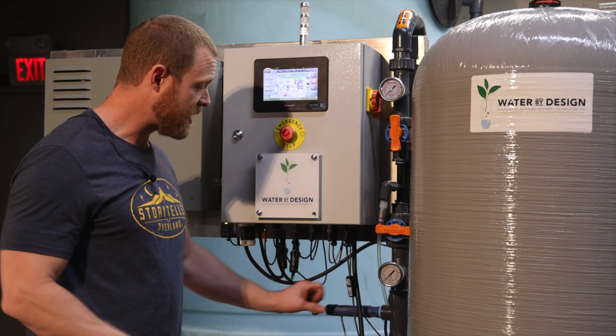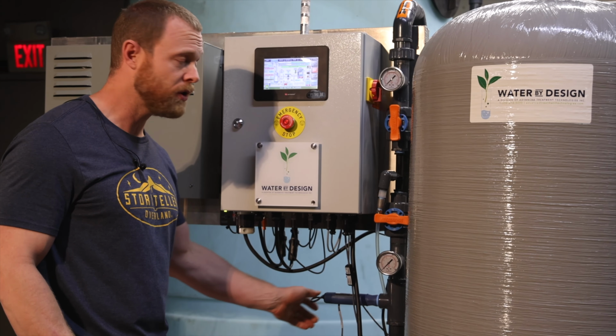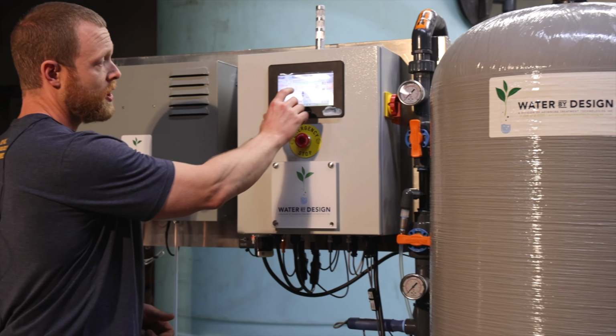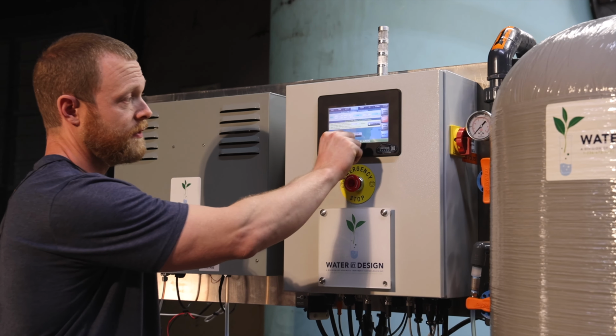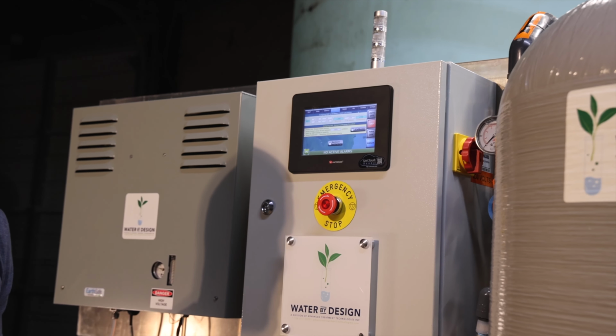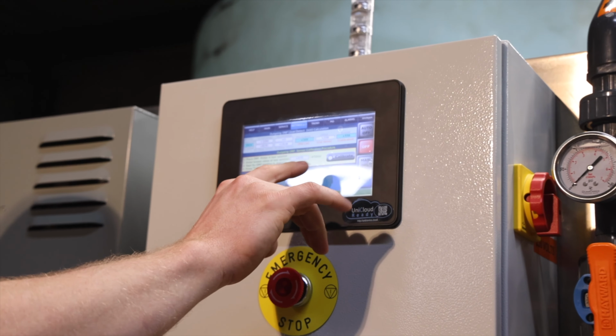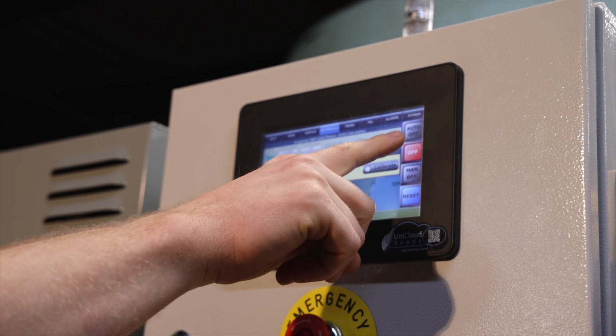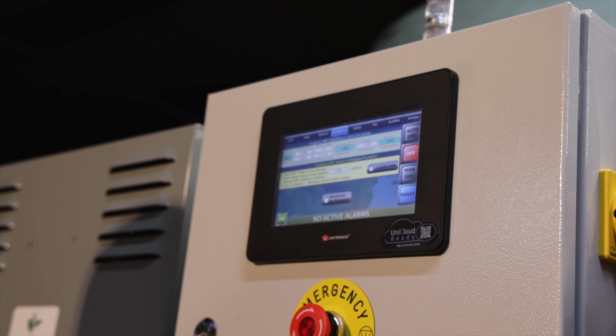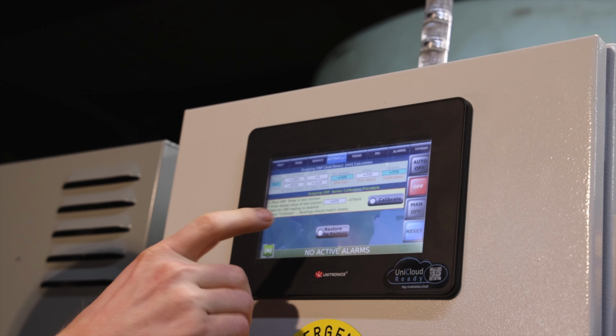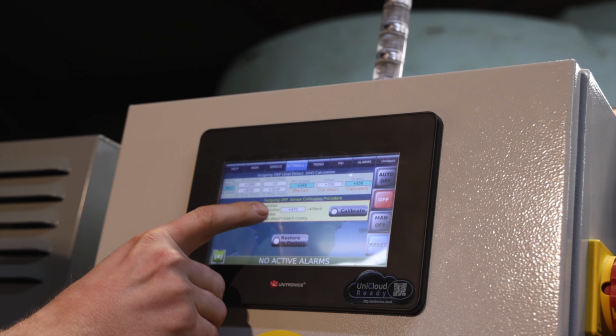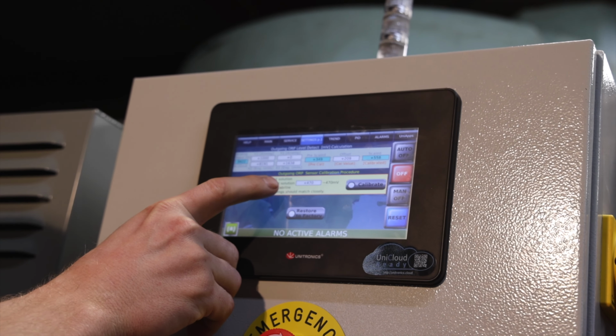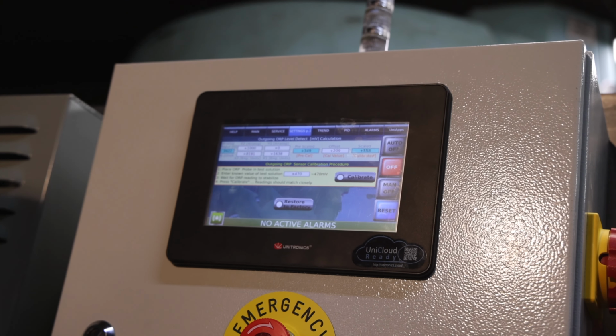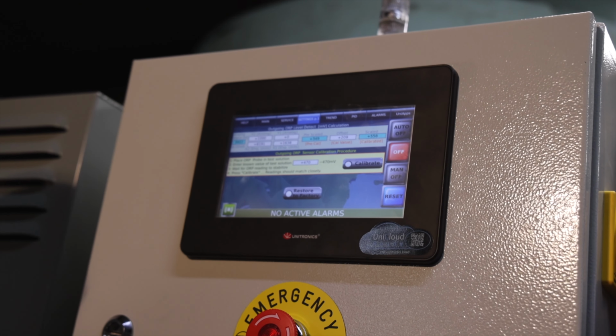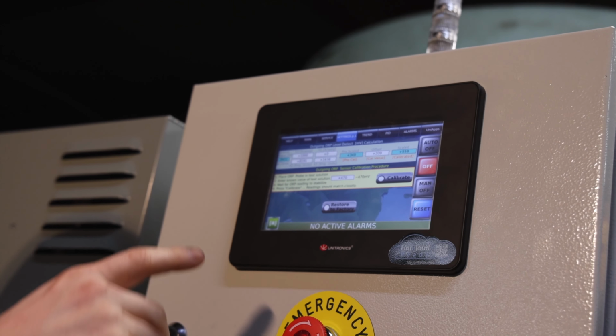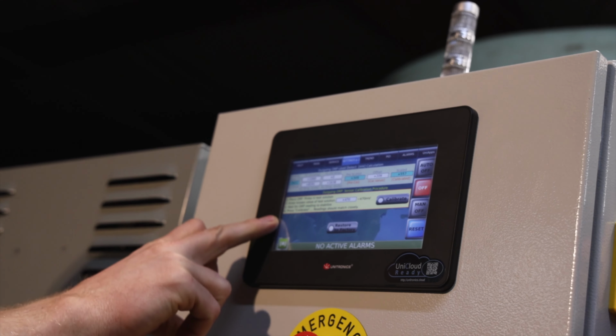So after all this is done, you'll remove this, you just unscrew it, you'll take it out, and you'll go to your settings, the first settings page from the main screen. So you'll see on here, you have a couple different things that you're going to pay attention to. You have your value that's showing you what your current ORP level is. And in this box right here, we have this positive 470. This is the value that we're going to use to calibrate to. That should always be 470. You shouldn't have to mess with that. It should be right there. All these directions, by the way, are also right here on the screen.